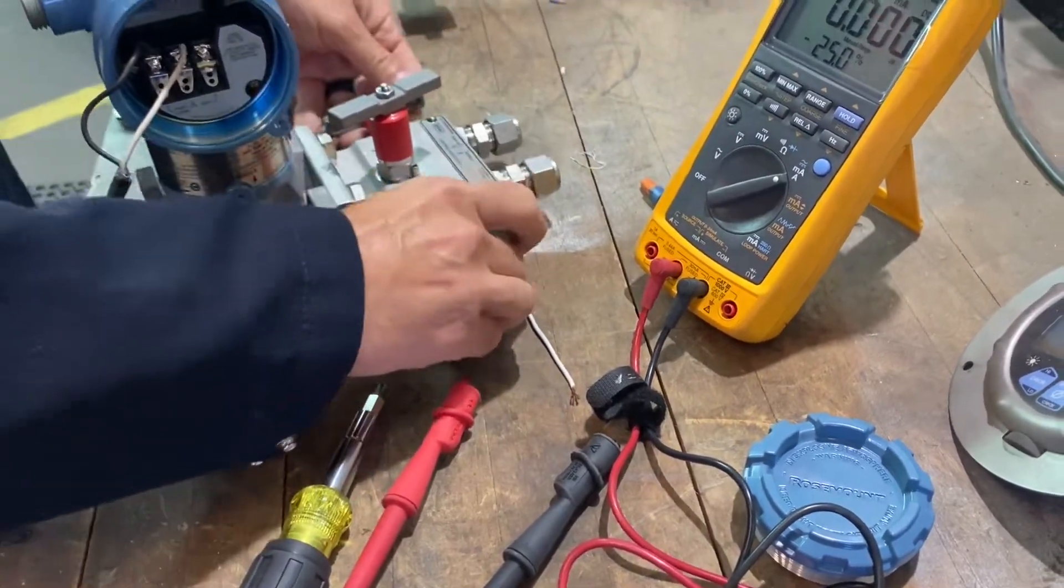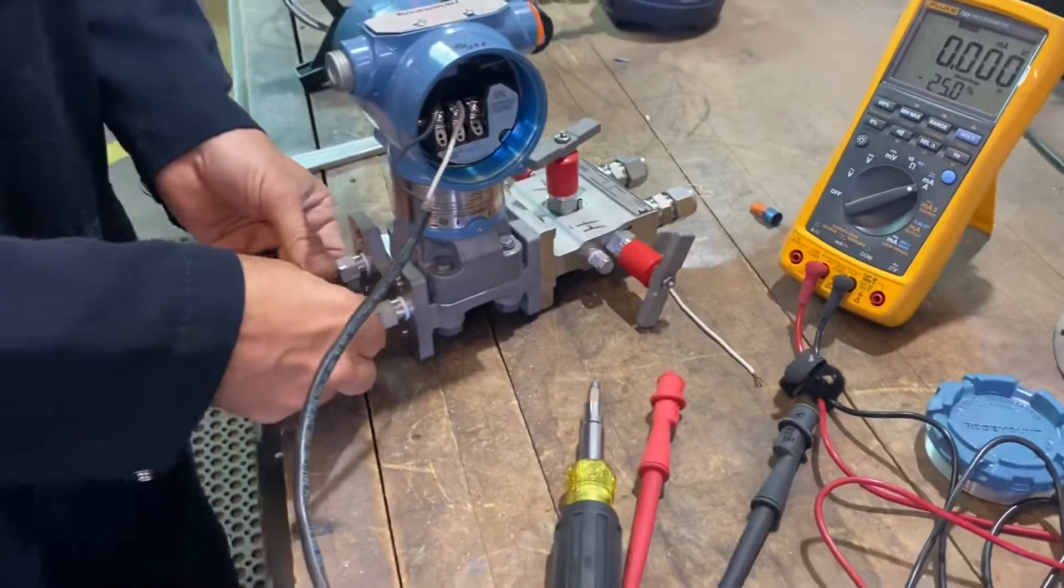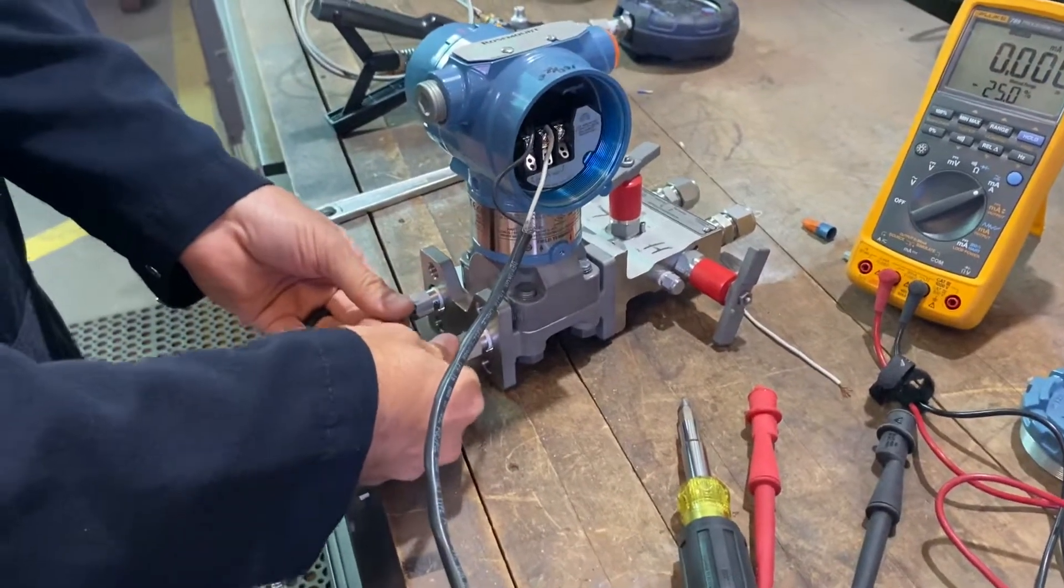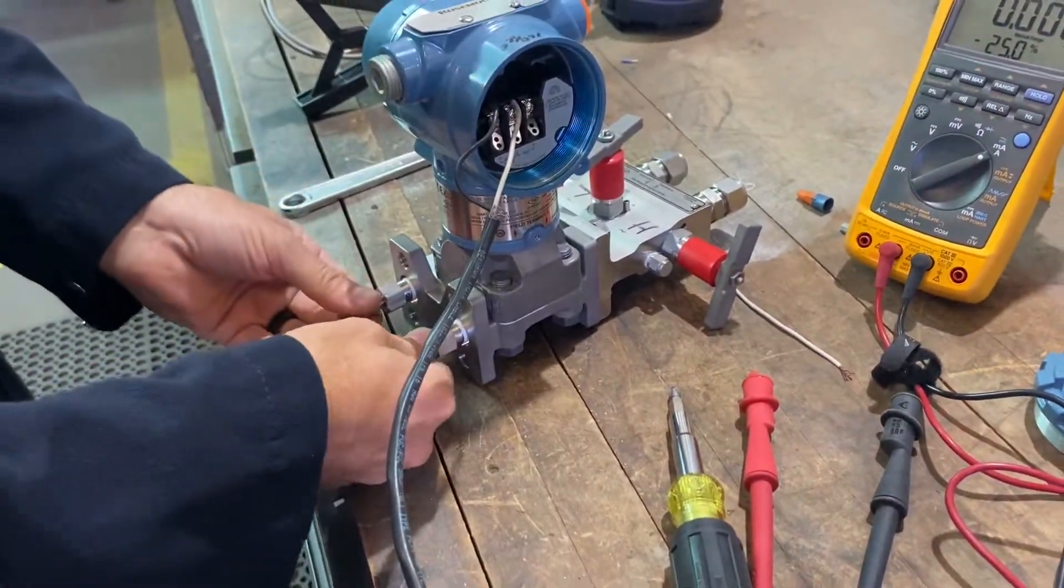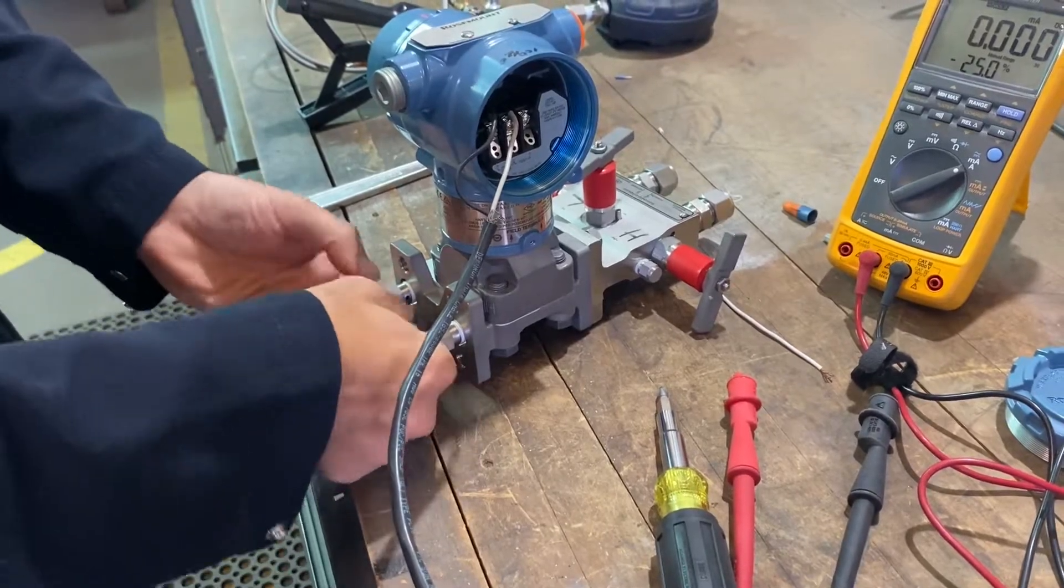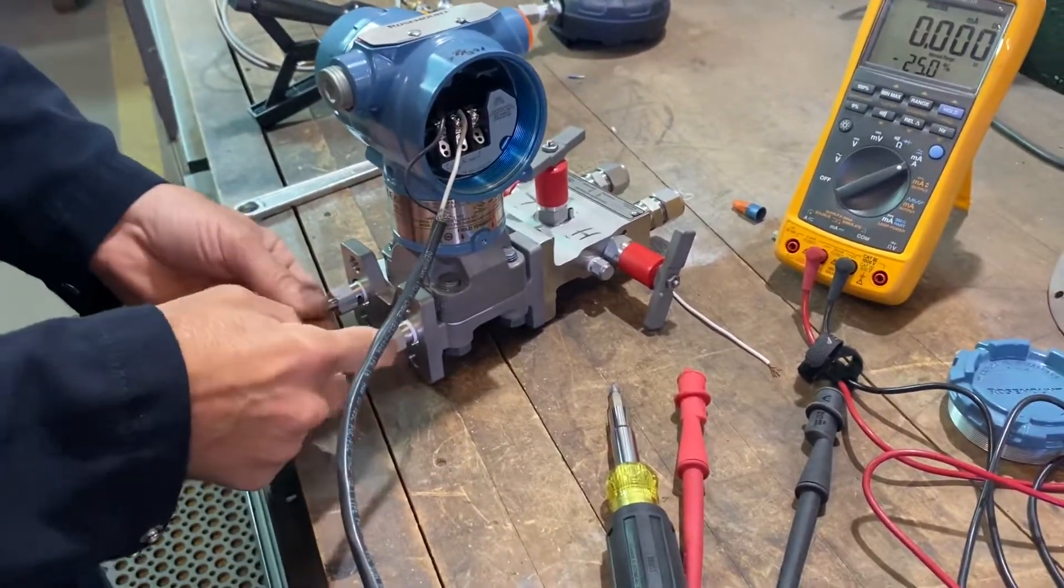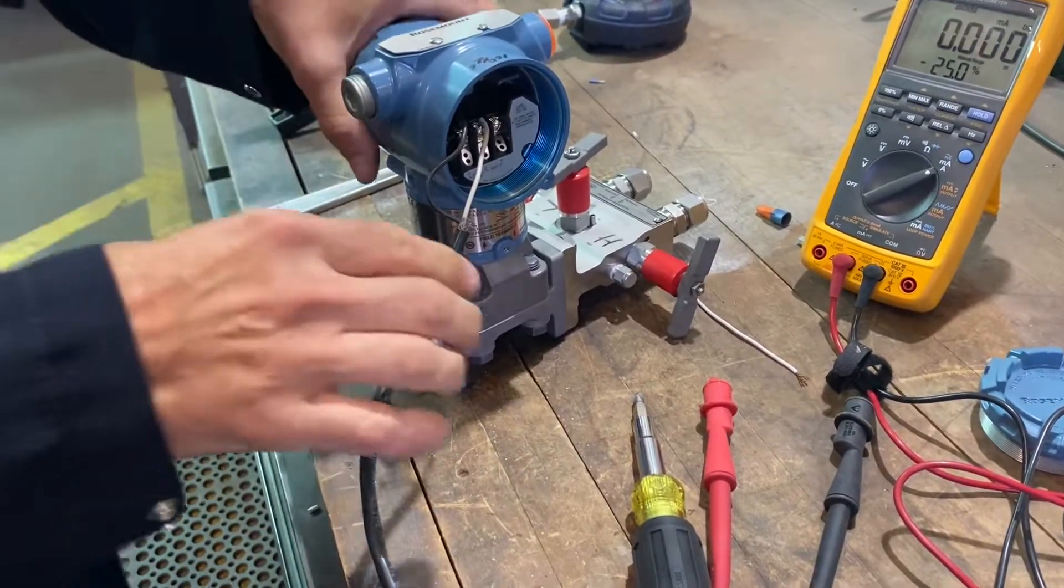Now, the other thing you want to do is you want to check the zero of the meter to make sure it's right. And the way to do that is, you block the meter completely in. After you block the meter in, you take the bleeders out, or at least loosen them, and then you should have zero.